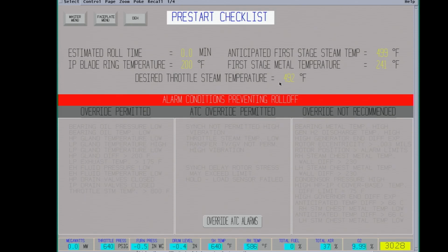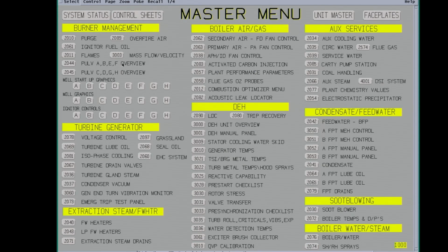So I'll have to sit at valve transfer for a while until these temperatures equal. The important thing is to try to hold the plant pressure and temperature uniform, otherwise it extends the hold times. Both throttle and steam are pretty good at 640 each one.